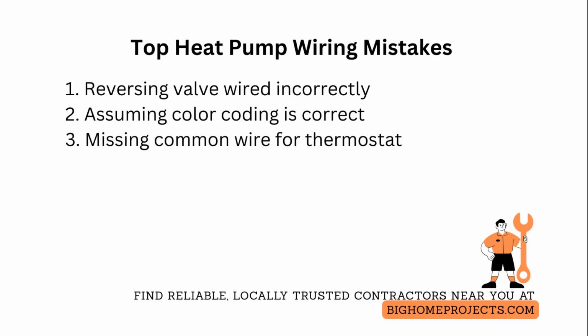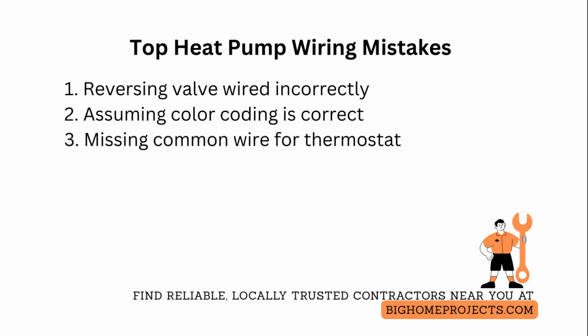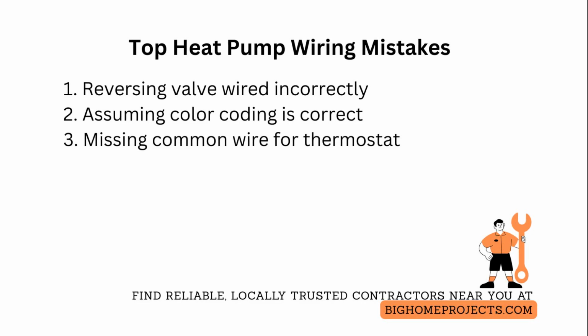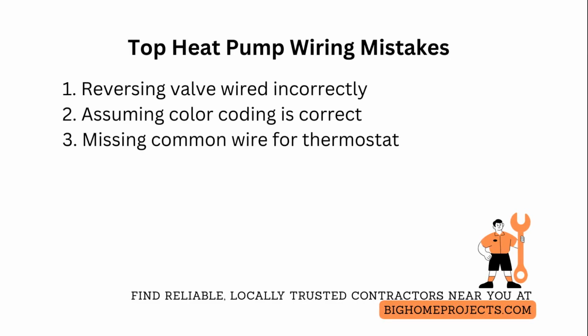One of the biggest installation issues is lacking a common wire for smart thermostats, resulting in intermittent reboots and lost schedules. The clear fix is to run a new common conductor from the control board or install a compatible power extender kit from the thermostat manufacturer.